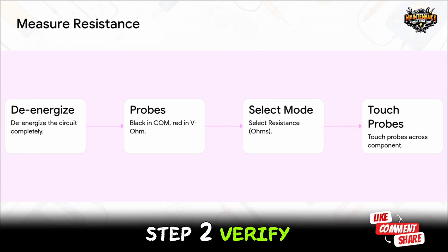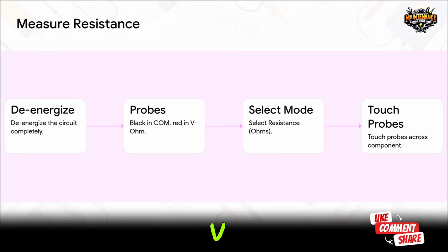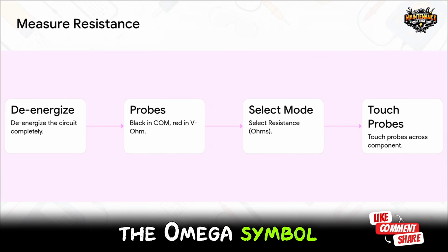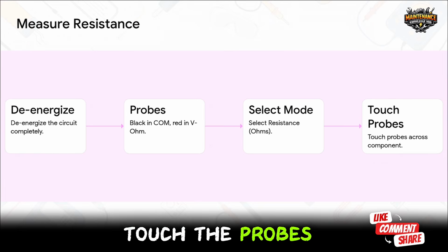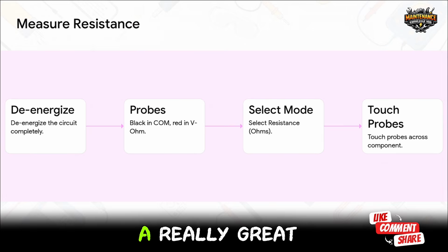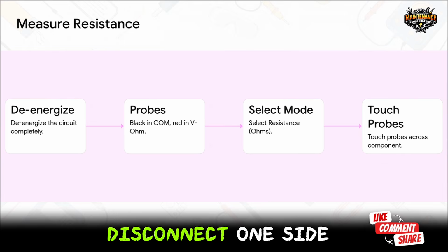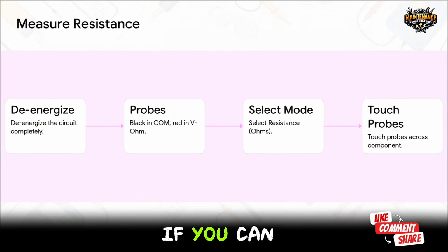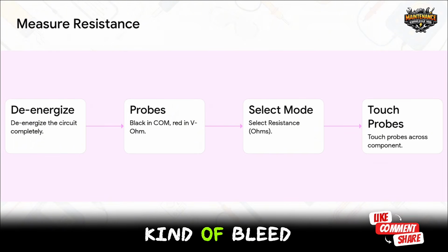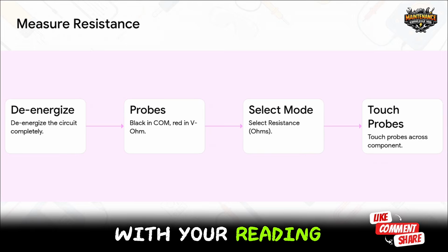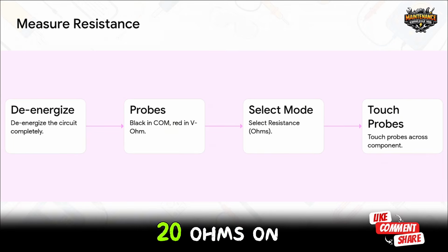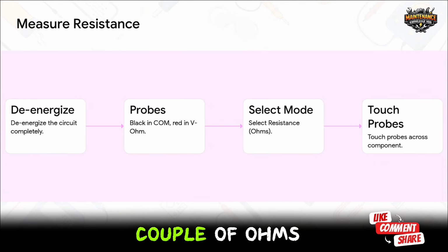Step 2, verify your black probe is sitting in COM and move that red probe back over to the V-ohm terminal. Step 3, turn your dial to resistance, the omega symbol, and step 4, touch the probes directly across the component. A really great pro tip here, disconnect one side of the component from the circuit, if you can. That way other wiring won't bleed over and interfere with your reading. Using this method, you might read 20 ohms on a heater element, or just a couple of ohms on a motor winding, depending on how big it is.